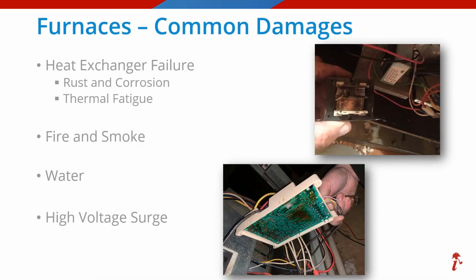Sometimes we forget that high voltage surges can and do happen in fall and winter and might cause damage to anything electronic within the furnace system. Here we see some common items affected. The top photo is a transformer and the bottom a furnace control board. But we can't forget about all those other items we outlined earlier, such as the thermostat, the draft inducer motor, gas valves, and of course the blower motor. Again, you will need an HVAC technician with the proper training and tools to make determinations of high voltage surge. So next we're going to review a couple common claim scenarios from real furnace claims.